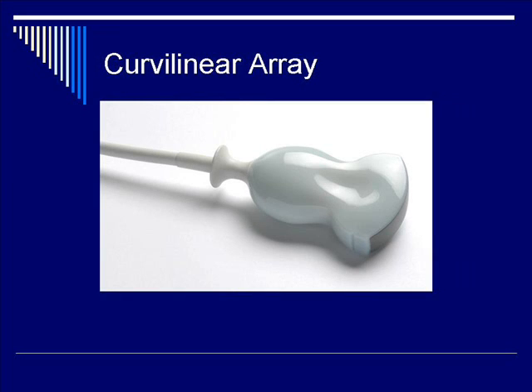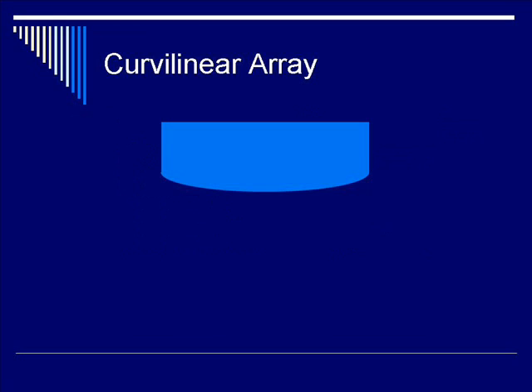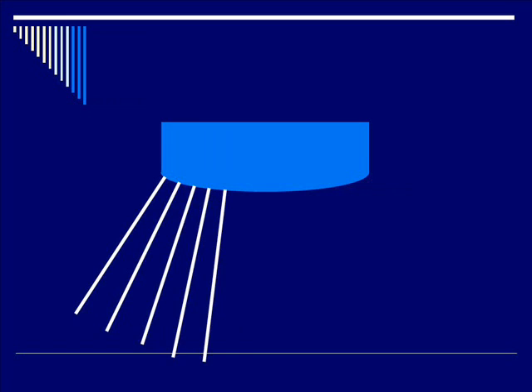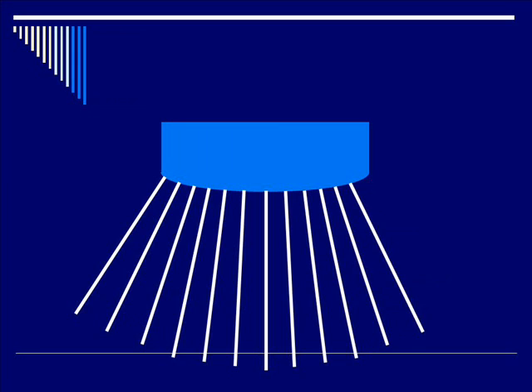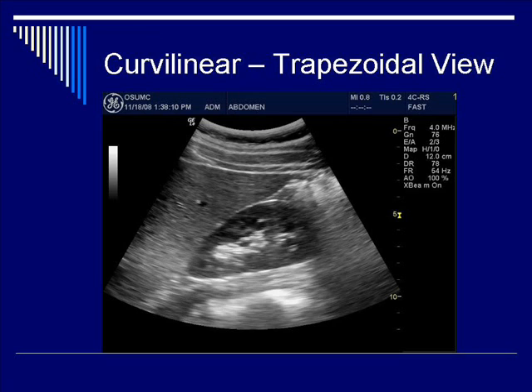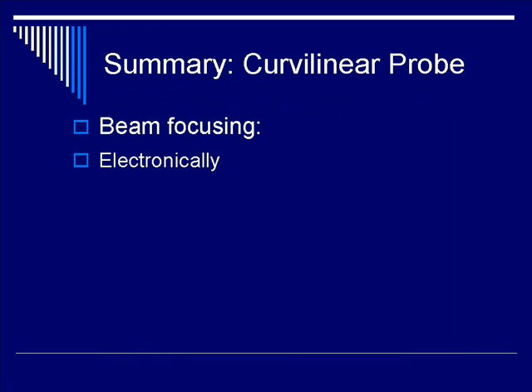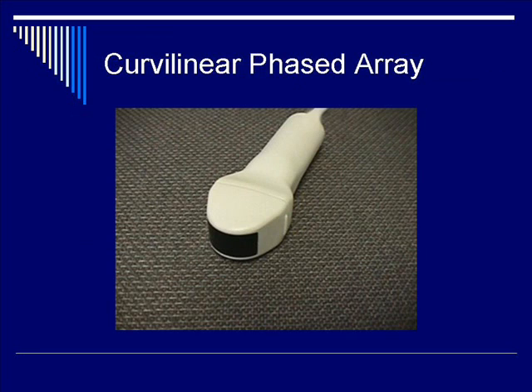Next, let's talk about curvilinear array. Typically it consists of 128 elements, again like the linear array. One element or a subset of elements are scanned sequentially. Focusing is done electronically, and it yields a trapezoidal scan pattern. Here is a cartoon of a curvilinear array. As it gives off the ultrasound pulses and scans sequentially from left to right, we create a trapezoidal scan pattern of the resulting soft tissue of interest. Here you see an example of the trapezoidal pattern of the Morrison pouch. In summary, the curvilinear array beam is focused and steered electronically, sequentially scanned via a subset of transducer elements.